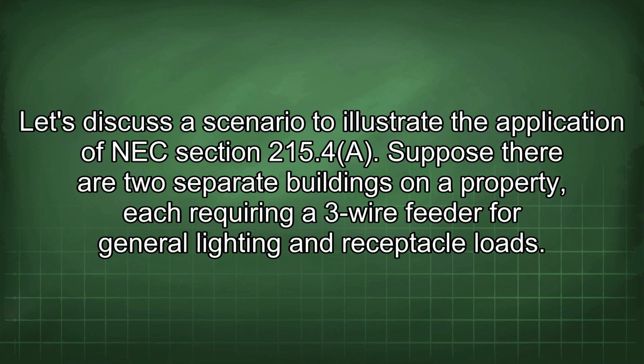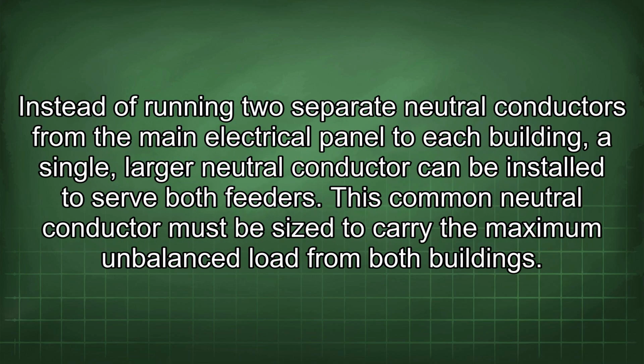Suppose there are two separate buildings on a property, each requiring a 3-wire feeder for general lighting and receptacle loads. Instead of running two separate neutral conductors from the main electrical panel to each building, a single, larger neutral conductor can be installed to serve both feeders. This common neutral conductor must be sized to carry the maximum unbalanced load from both buildings.